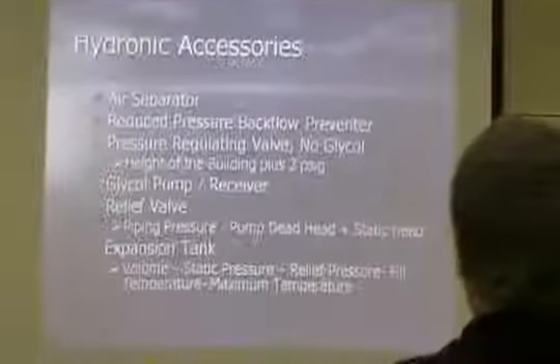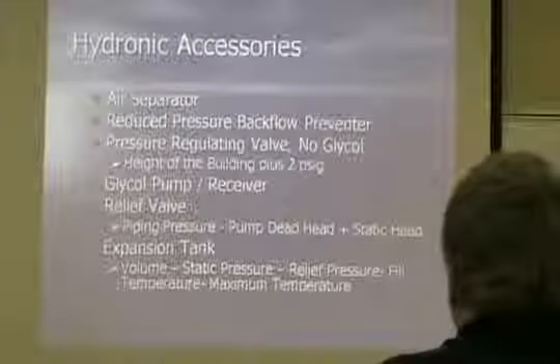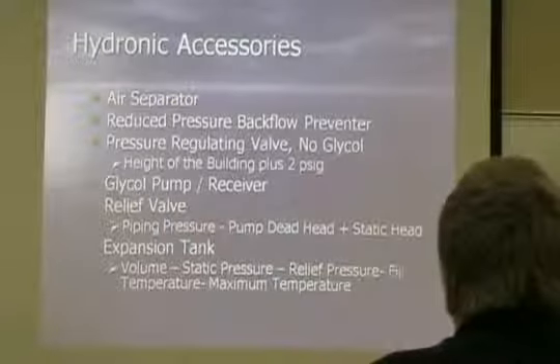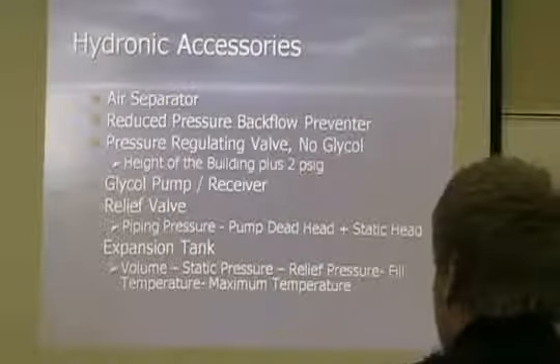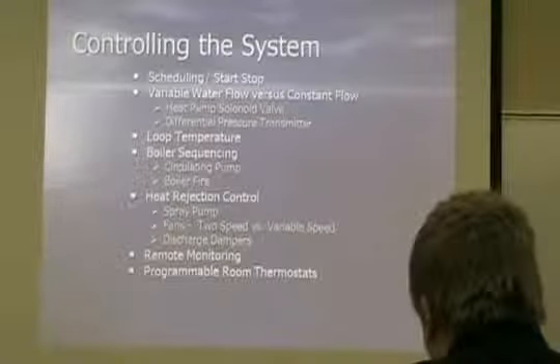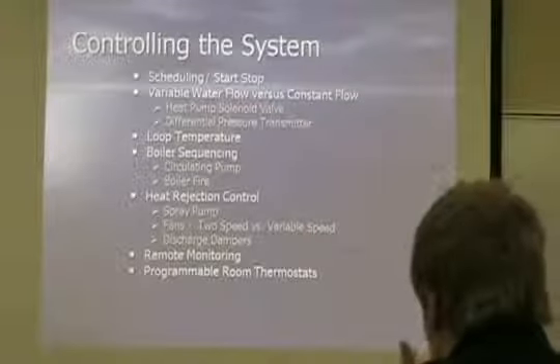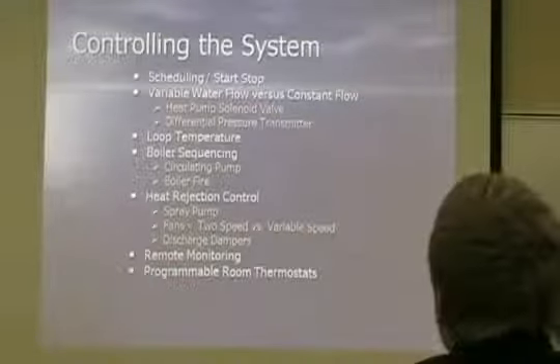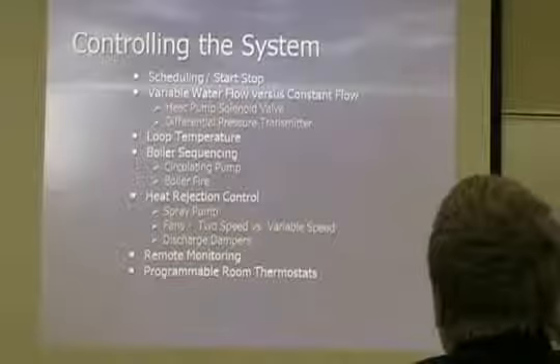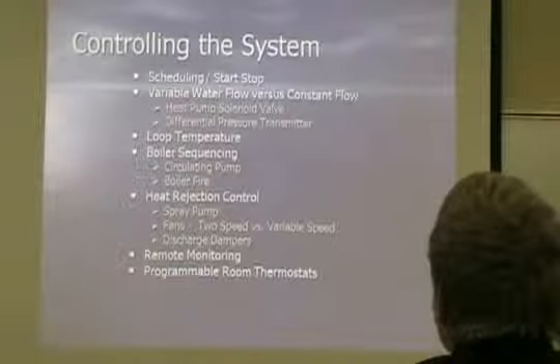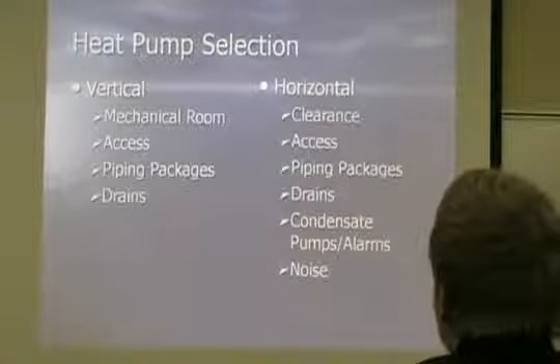You know, it is a closed water system, so you would have to have an expansion tank and a relief valve. We talked about the deadhead plus static head of your pumps, how to size that. We're going to review those things again. Controlling the system, there's scheduling, you can do variable volume applications, we talked about that. I want to get into the drawing. We'll come back to some of this.